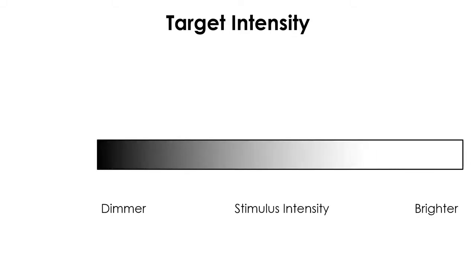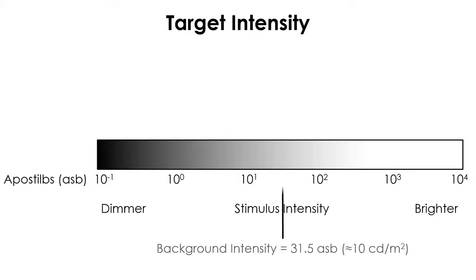Next, the luminance unit for the background and stimulus in visual field testing is called the Apostil, or ASB for short. This is a type of luminance measurement reflected from a surface and has been used in quantitative manual perimetry. The background luminance of the testing bowl is set at 31.5 ASB, which is bright enough to saturate rod photoreceptors, so visual field testing is carried out in the photopic range within which Weber's law holds.